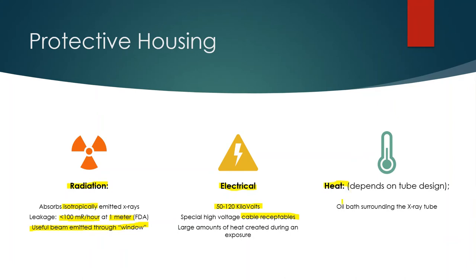Heat dissipation depends on tube design, but for the most part there is an oil bath surrounding the glass x-ray tube. Heat moves away from the x-ray tube, heats up the oil, the oil heats up the tube housing, and the tube housing heats up the air in the room — and that is how heat is dissipated.